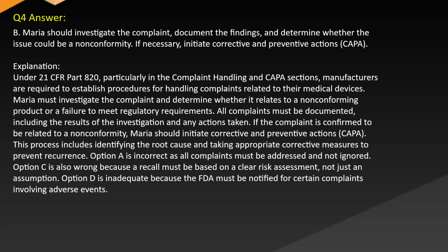All complaints must be documented, including the results of the investigation and any actions taken. If the complaint is confirmed to be related to a nonconformity, Maria should initiate corrective and preventive actions (CAPA). This process includes identifying the root cause and taking appropriate corrective measures to prevent recurrence. Option A is incorrect as all complaints must be addressed and not ignored. Option C is also wrong because a recall must be based on a clear risk assessment, not just an assumption. Option D is inadequate because the FDA must be notified for certain complaints involving adverse events.